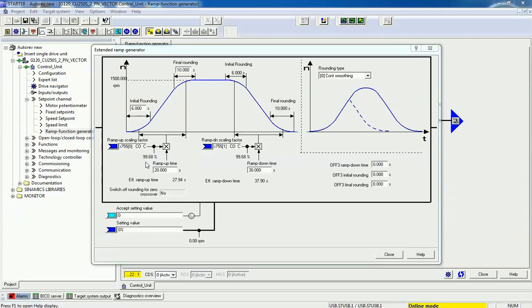You can vary the percentage and see how the effective ramp up time and ramp down time change accordingly. I am decreasing the ramp up scaling factor and the effective ramp up time varies. Now I decrease the ramp down scaling factor — you can see the effective ramp down time is also changing. When I enable the drive, in approximately 30 seconds this motor will reach maximum speed.